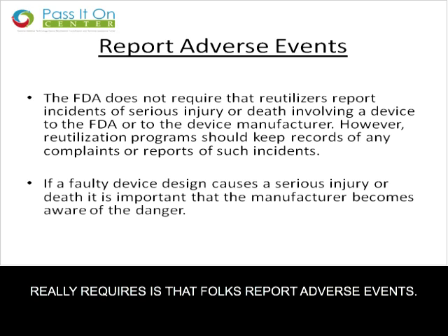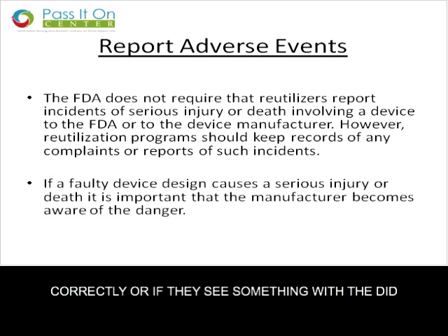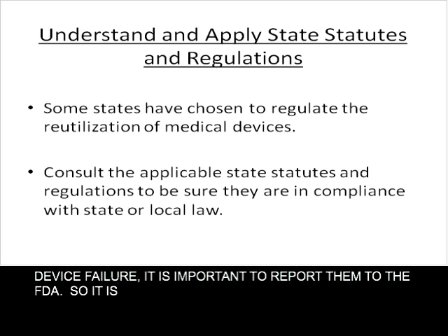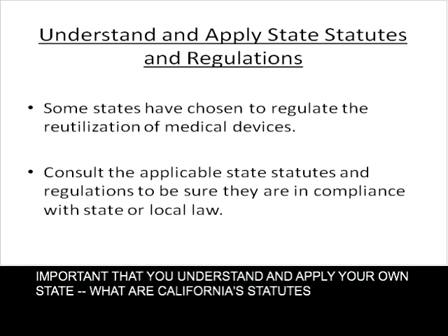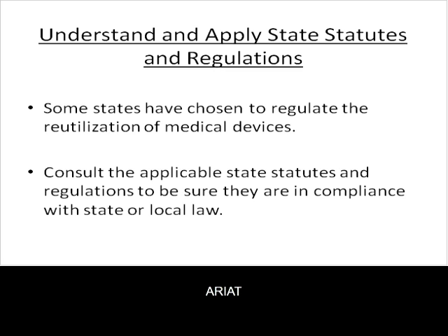As I said, we encourage folks to have qualified technicians for their reassignment, refurbishing, and also recycling activities, if they're tearing the equipment apart. Part of what the FDA really requires is that folks report adverse events. We have our reuse programs doing this also: if something doesn't function correctly, or they see a device failure, it's important to report those things to the FDA. And we have had several incidents where people have been able to do that.